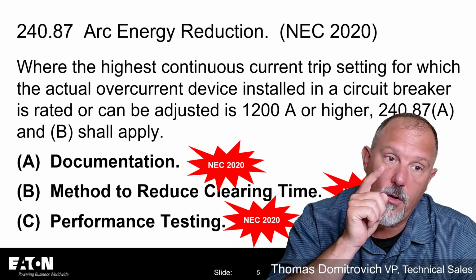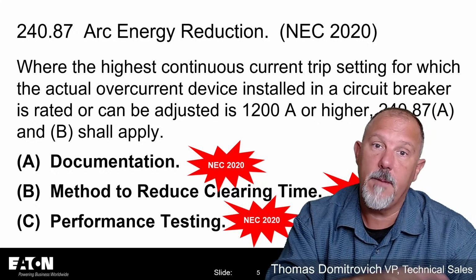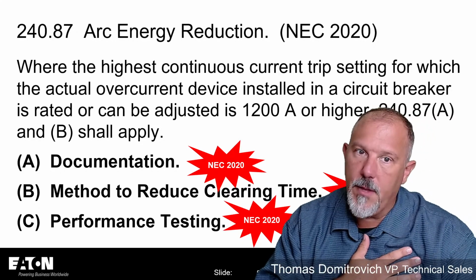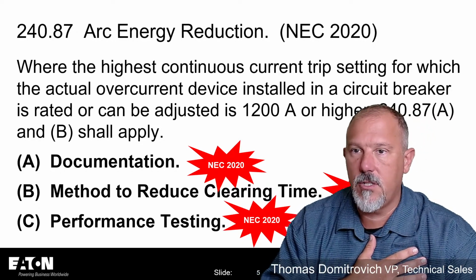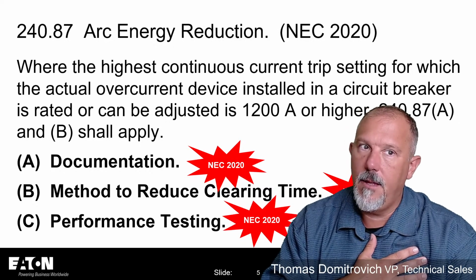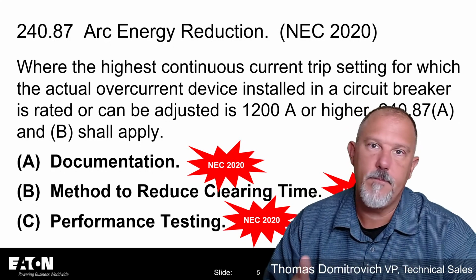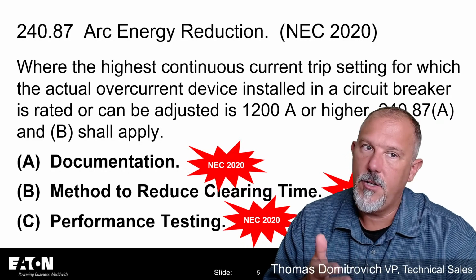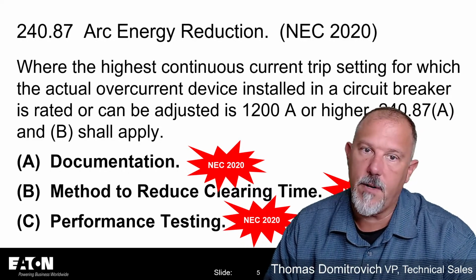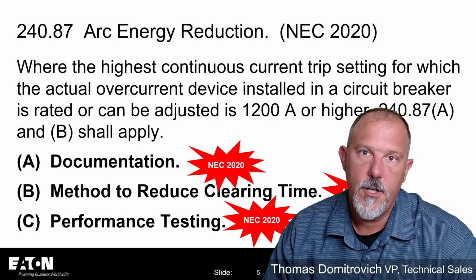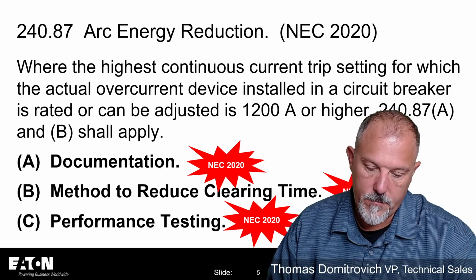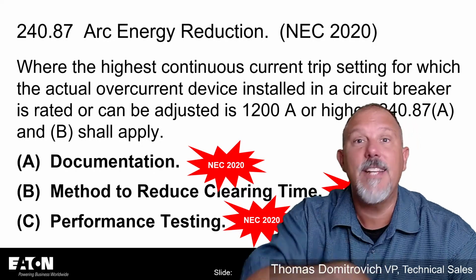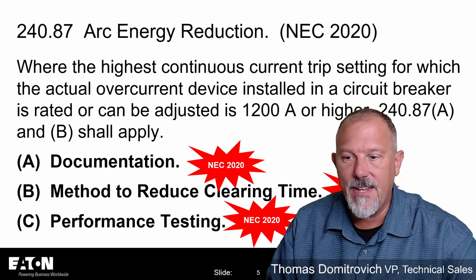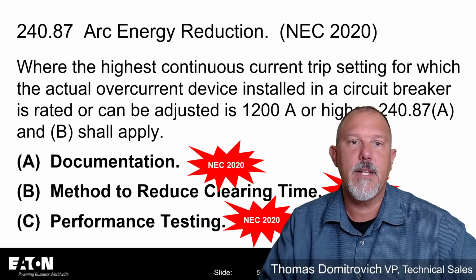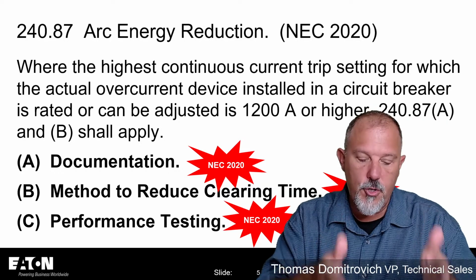So you've got to have this clear up front, but I don't know that anybody makes a 1,000 amp sensor or a 1,000 amp plug. They'll have a 1,200 amp and they'll have an 800 amp. You're not going to have that 1,000 amp plug. If you have a 1,200 amp breaker, you're into 240.87. So hopefully you catch that on plan review. You get that when you're looking at the plans, you're looking at the drawings. Make sure you get that information.